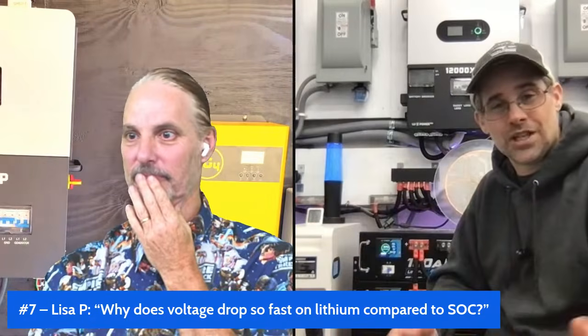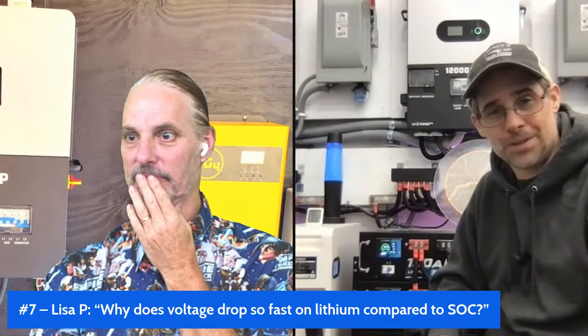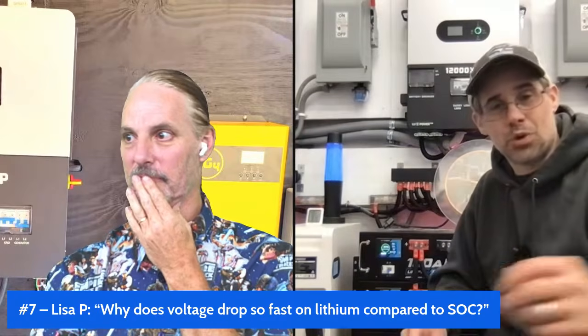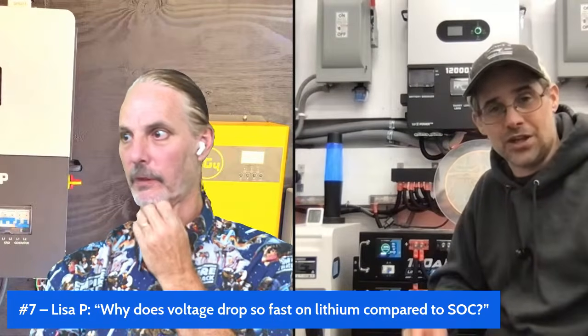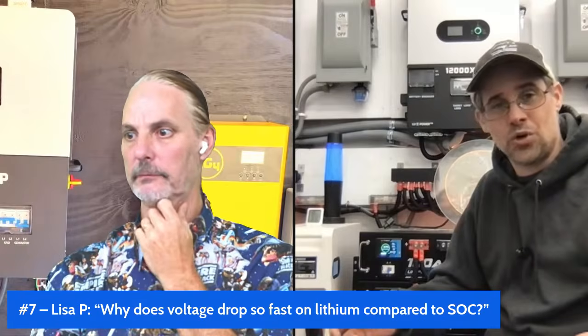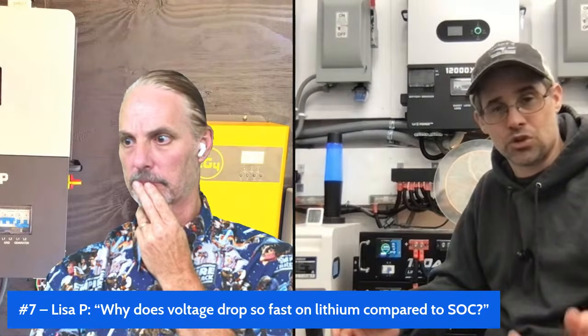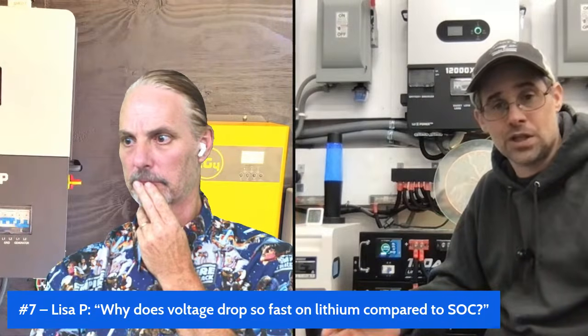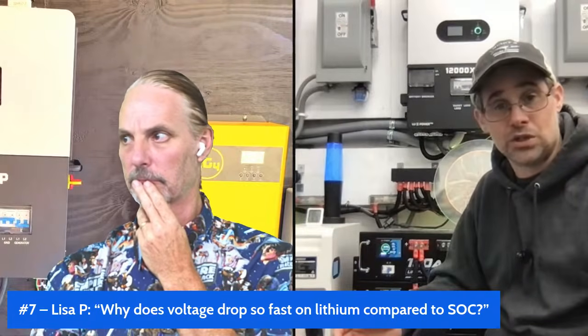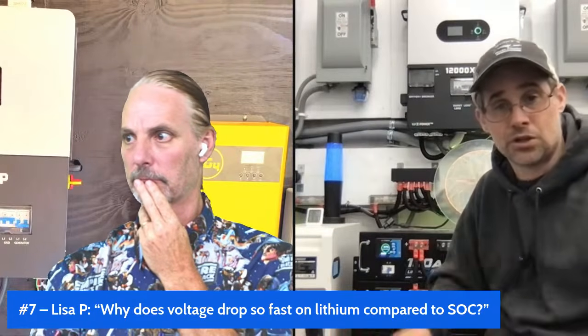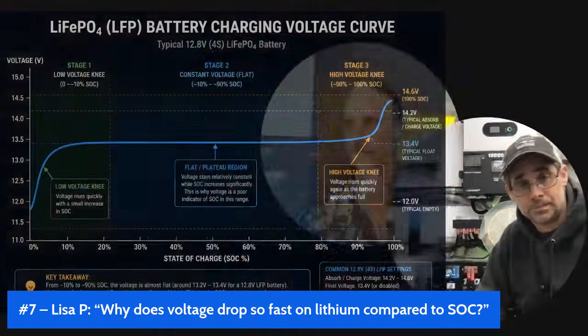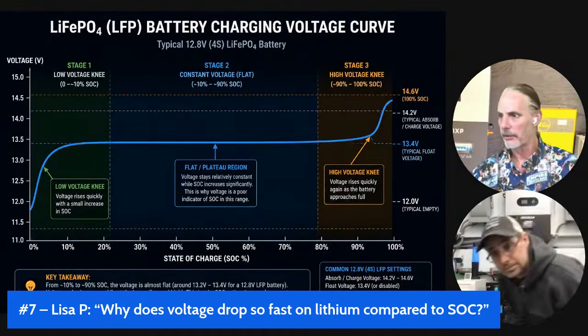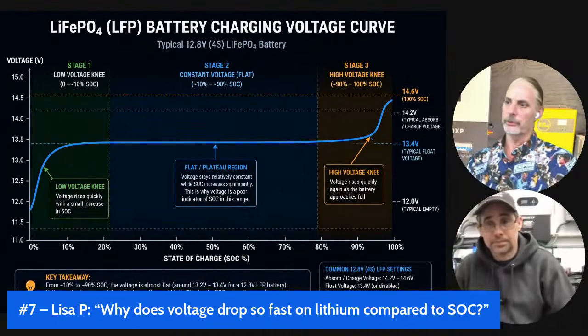If you're using 2 gauge wire, there's a lot more resistance in 8 feet of 2 gauge than in 2 feet. Because the internal resistance of the batteries is so low, this makes a real difference. The battery on the end of the chain will always be lazy compared to the one closest to the inverter.